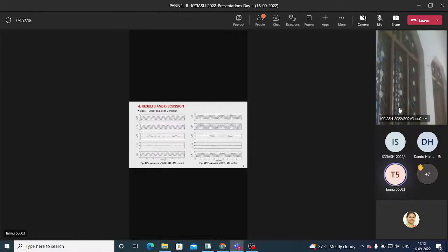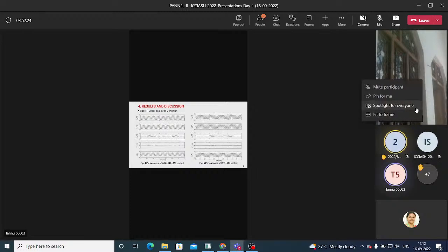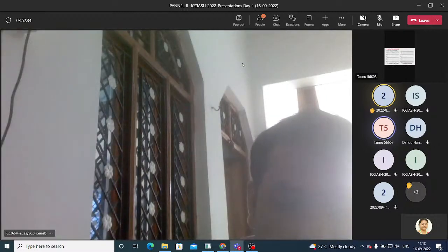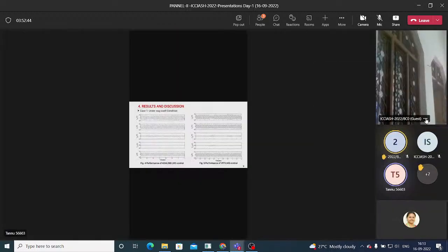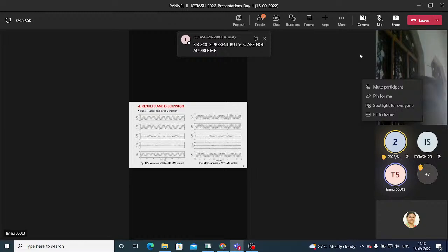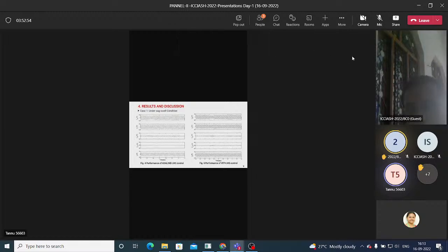So, result and discussion. MATLAB simulation results of the single-phase DVR with both control techniques are demonstrated to compare the work. The performance of the single-phase dynamic voltage restorer is evaluated under various dynamic conditions of supply voltage such as sag, swell, and harmonic distortion. In case 1, a 20% sag is introduced in the supply voltage during the time interval 2.5 second to 2.6 second for 5 cycles of supply voltage. Then from 2.9 second to 3 second, a 20% swell is introduced in the supply voltage, as shown in figures 4 and 5.